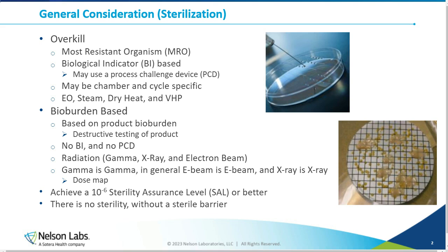So examples of bioburden-based sterilization are gamma, X-ray, and electron beam, E-beam for short. With that, we also are going to have situations where we're changing the dose, and how does that change affect things? In general, gamma is gamma, E-beam is E-beam, and X-ray is X-ray. Changing from one gamma radiator to another is generally not going to have a large effect on the product. You would need to consider and do a new dose map with your radiator, but in general, you're not looking at a revalidation or things like that.